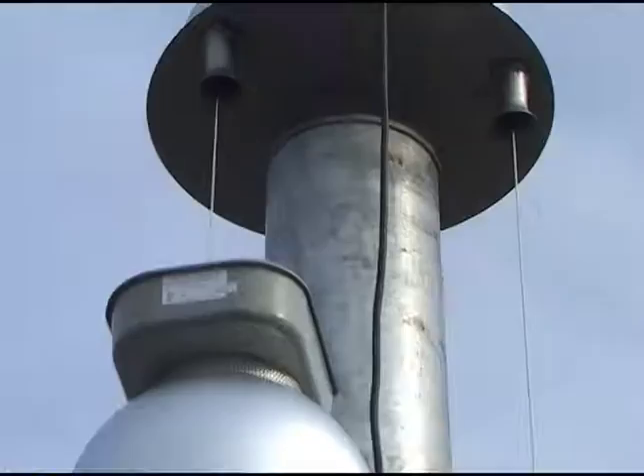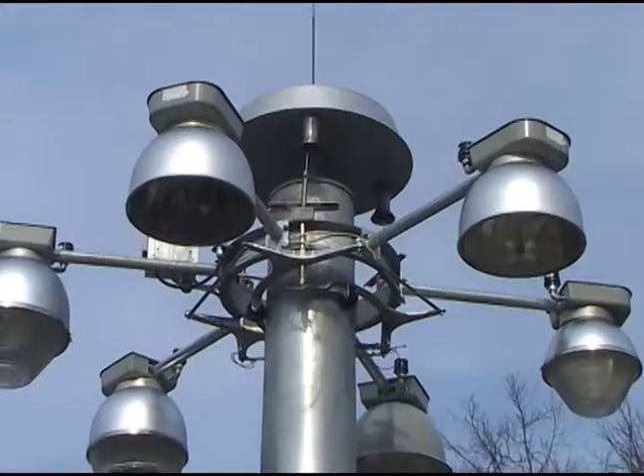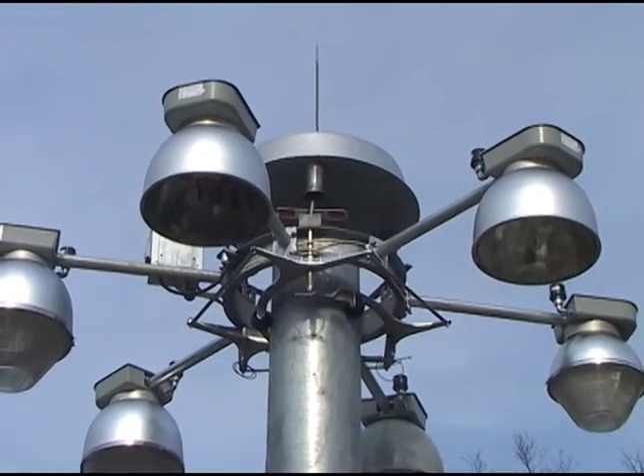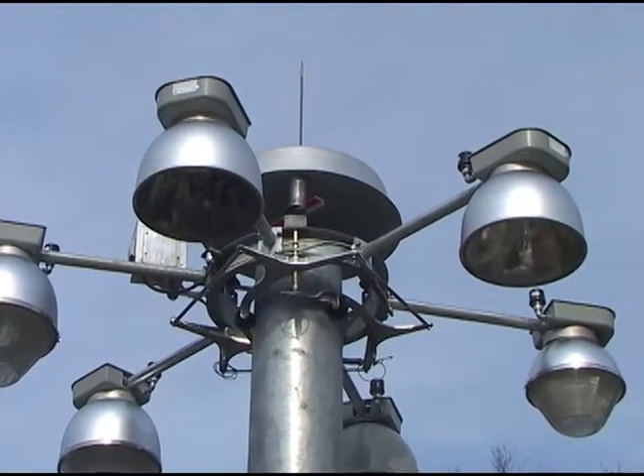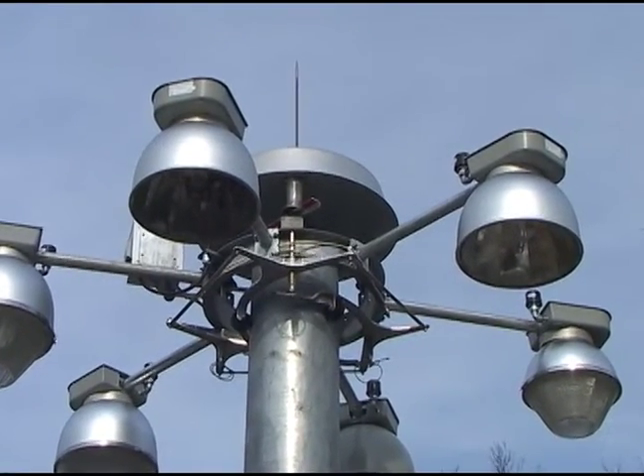Move the drum switch lever in the forward direction to raise the device to its farthest upward position while watching the flags and listening for the clutch to release. With the 3 flags rotating 45 degrees at the same time, the device is ready to latch.